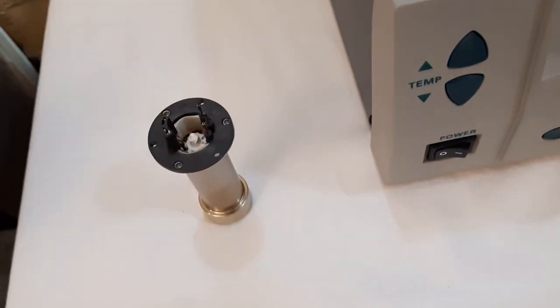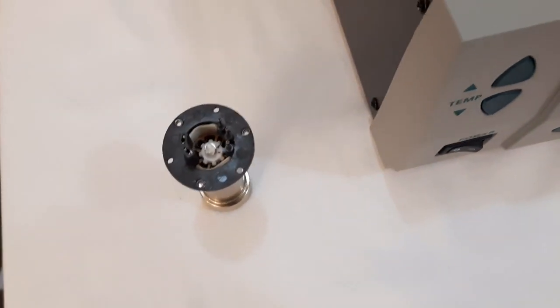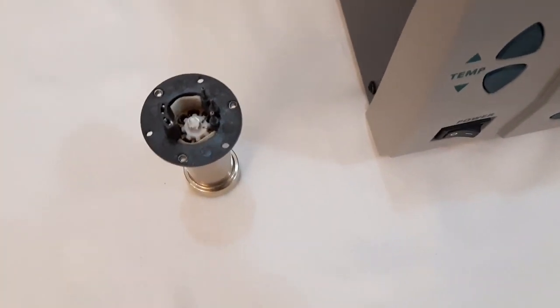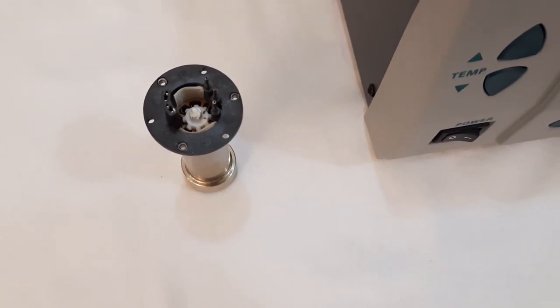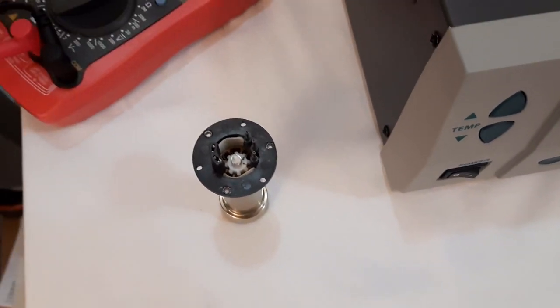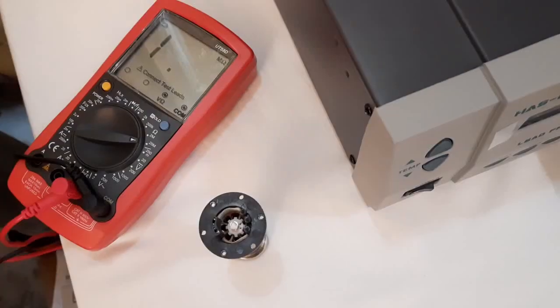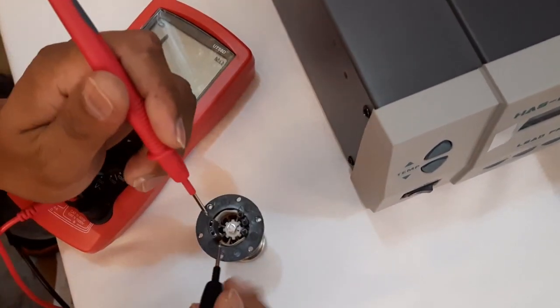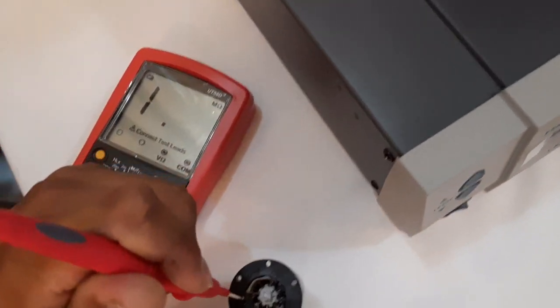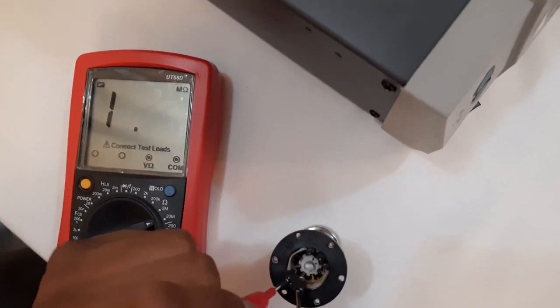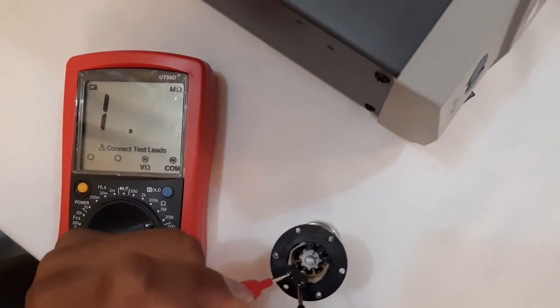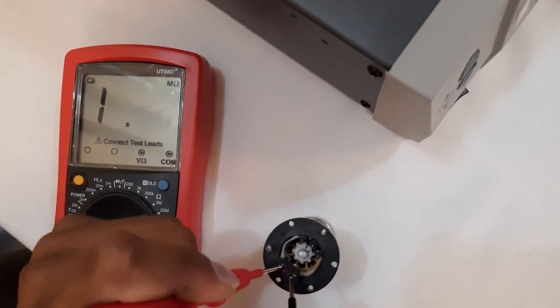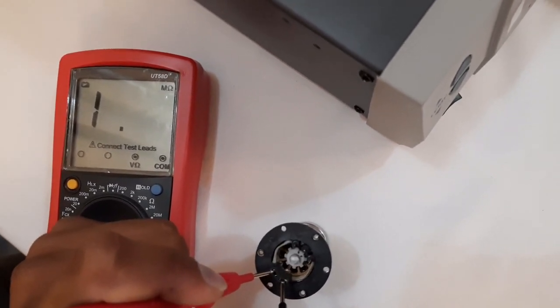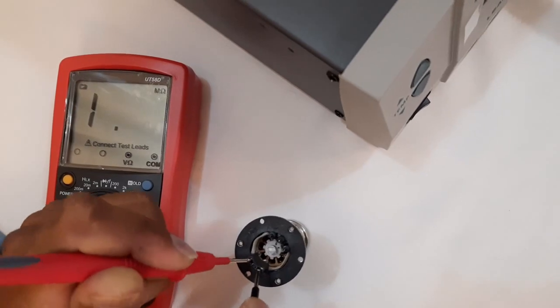So we will use a multimeter to verify the resistance of both these heating element and sensor. Since both are embedded in one enclosure, we will check the resistance between these two pins. These two pins are of sensor. So the resistance is almost more than 20 mega ohm. It means the sensor is faulty. Ideal resistance should be less than 50 ohm.